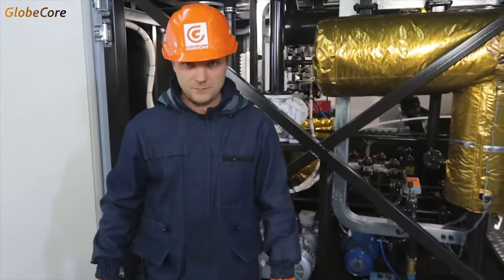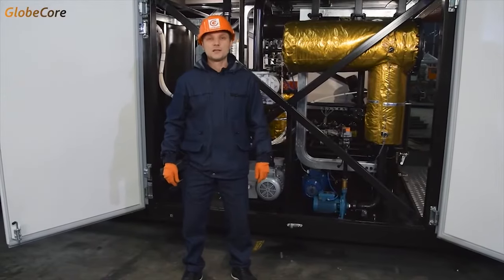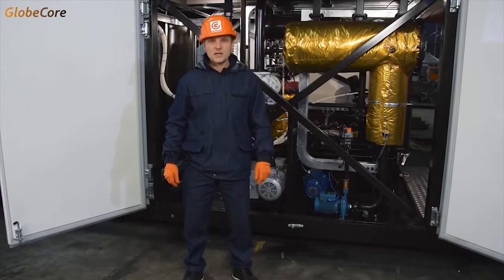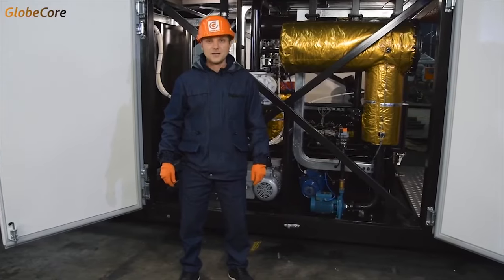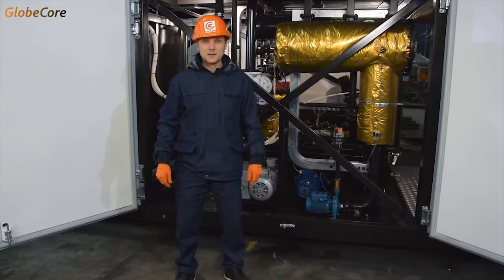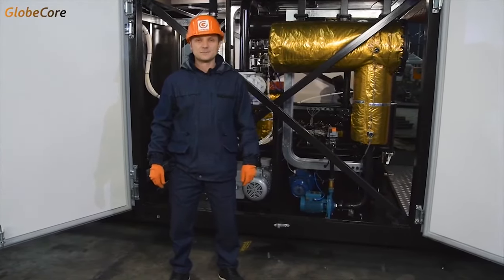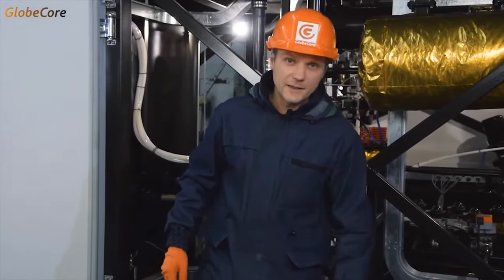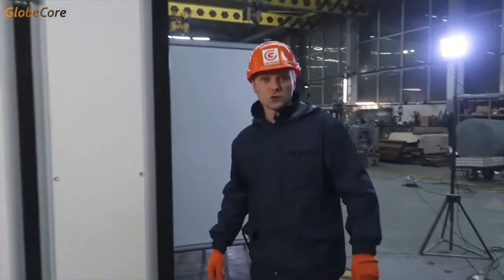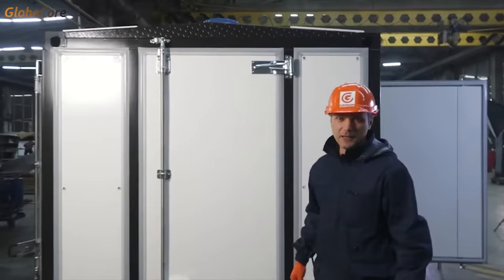Instead of this endeavor of dubious efficiency, this plant regenerates transformer oil in cycles until the entire transformer is cleaned out. The contaminants are removed not only from the oil, but also from the transformer components. The result of such periodic treatment is a significant extension of transformer lifetime. This is the essence of the regeneration process.